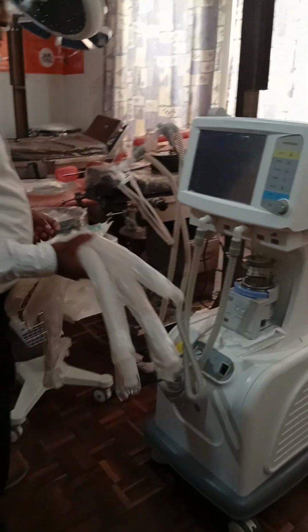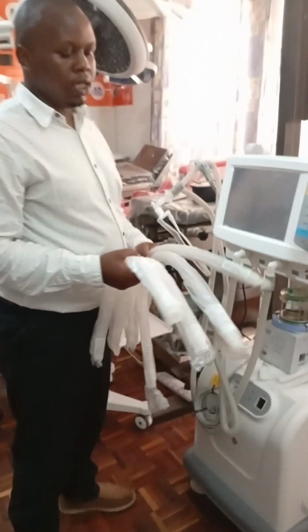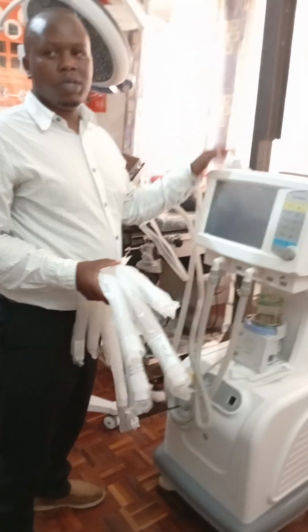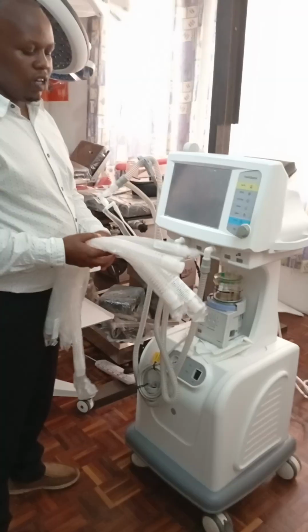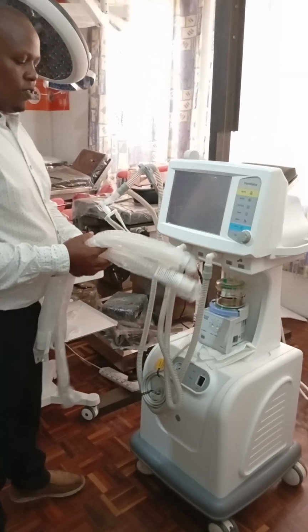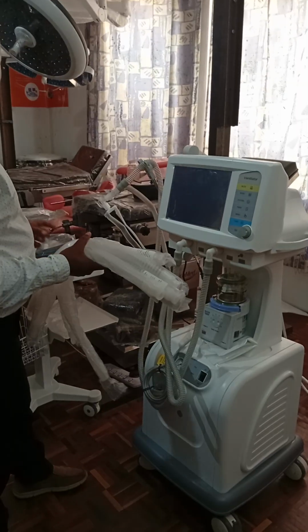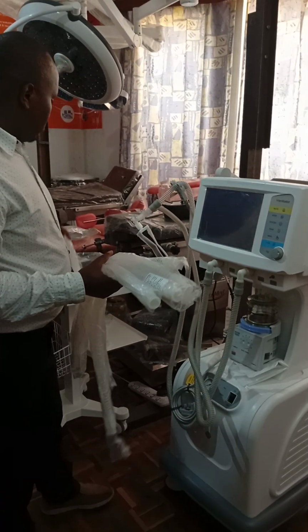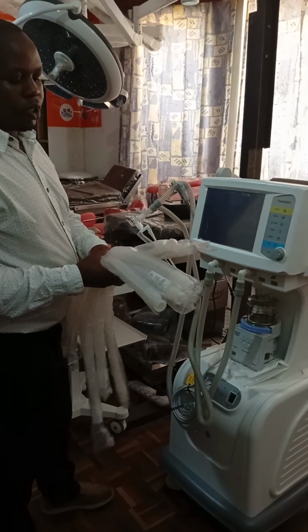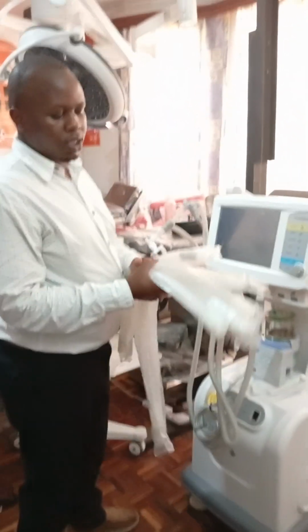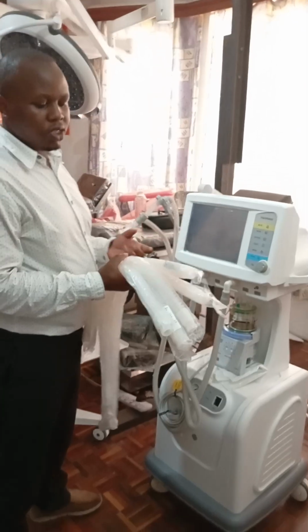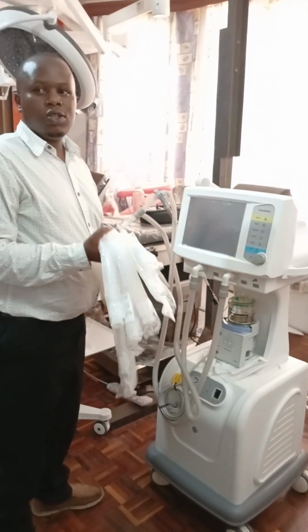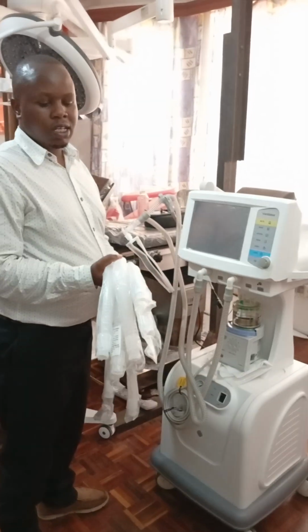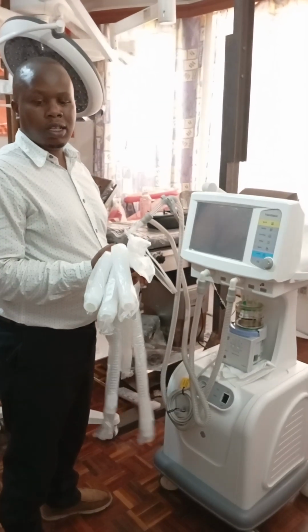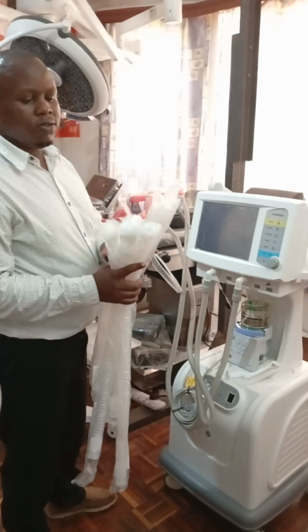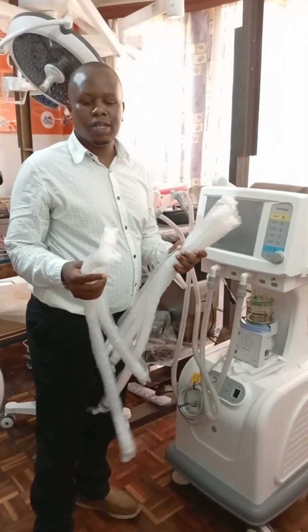This machine can be used for pediatric and for adult patients. Normally we have different tubings: 5 tubes for the adult and 5 for the pediatric. They are reusable. They should be cleaned after every 3 months or after use on each patient to avoid contamination. You need to clean with any soluble solvent, any disinfectant. After you clean, you rinse with clean water. After that, you have to blow dry them, or leave them to dry completely before use.